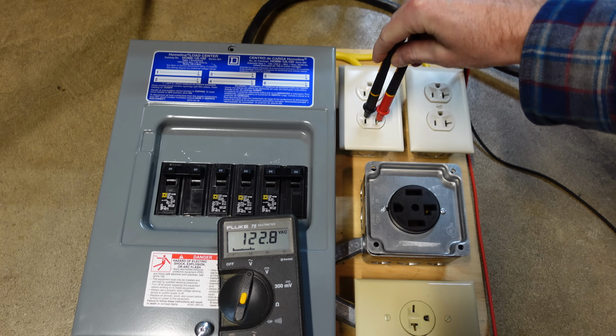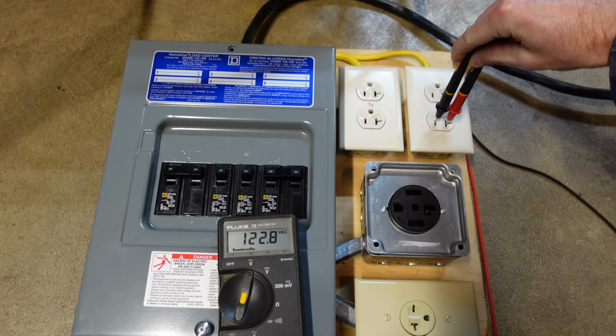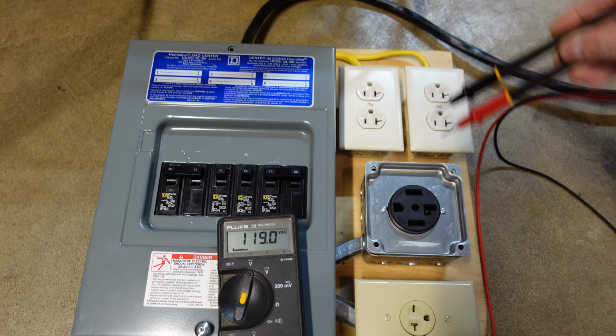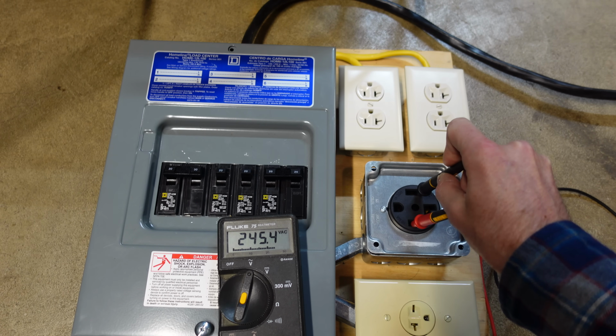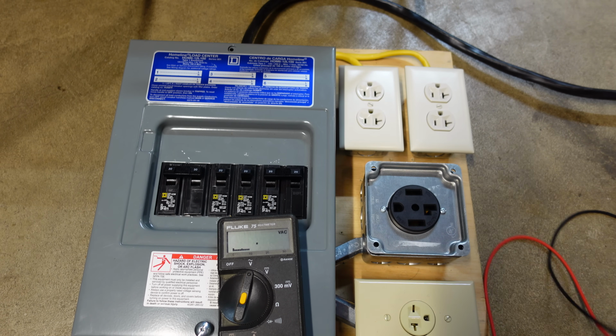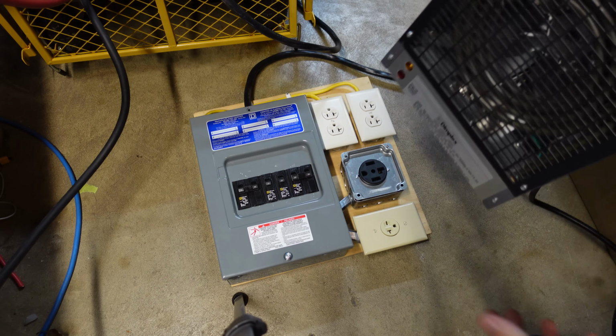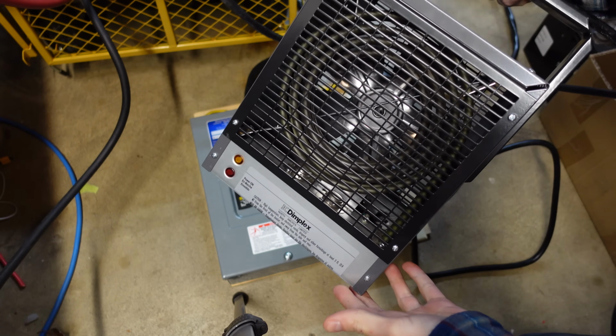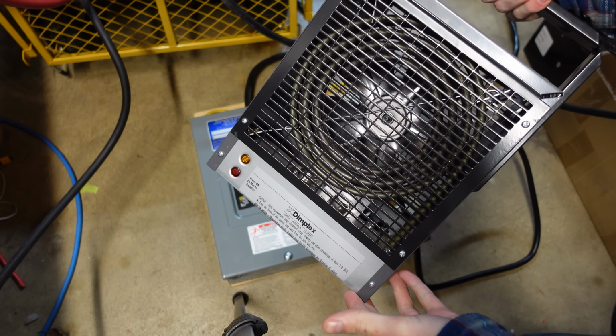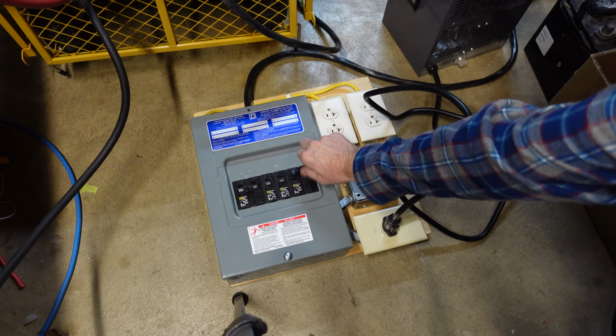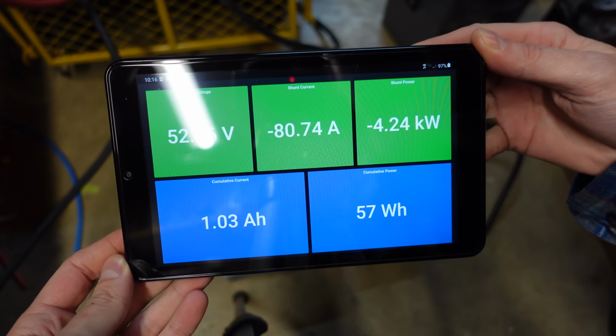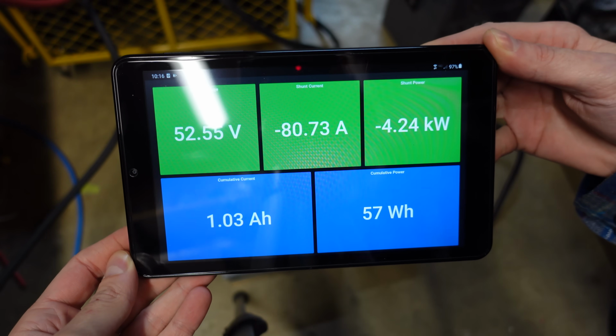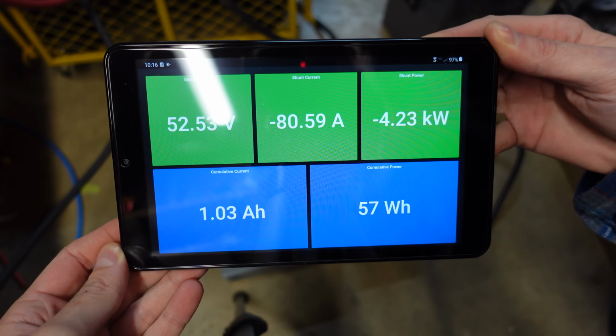Let's just check our panel voltages here. We've got 122 on leg 1, 122 on leg 2, and 245 volts across leg 1 and leg 2, so we're good to go there. Just going to plug in my space heater here. It's 240 volts, I think it's 4,500 watts or 4,000 watts, and turn it on. And you can hear the fans got quite a bit louder, and we're at 4.24 kilowatts. It's looking good.